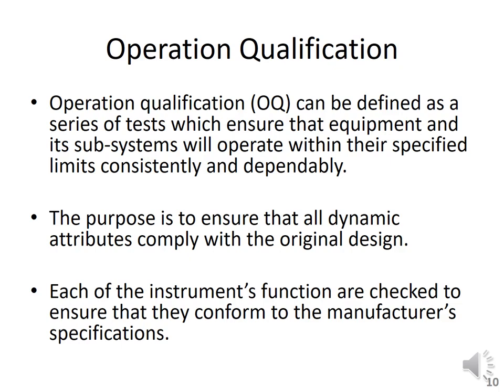Or in other words, if you are talking about an instrument, then we would say that operational qualification is usually performed before the instrument is handed over for use, right? So the purpose is to ensure that all the dynamic attributes comply with the original design of the machine, or original design of the work.